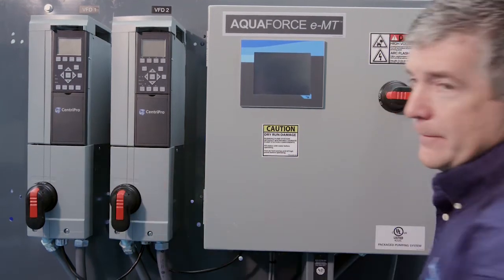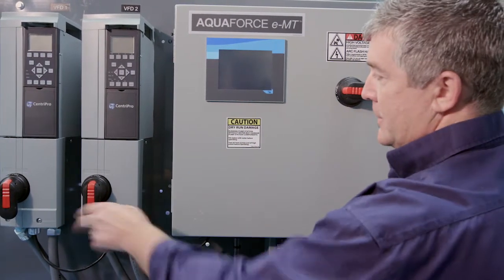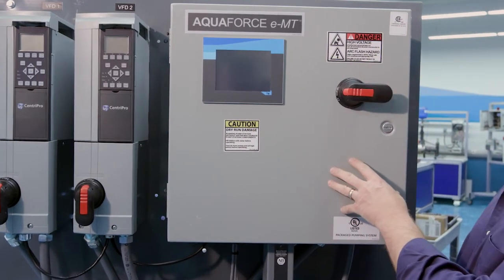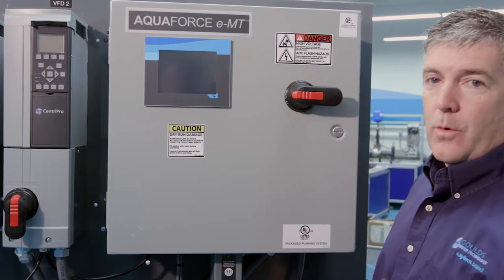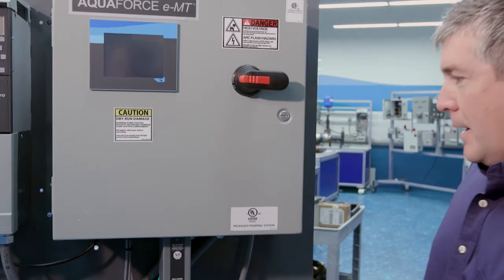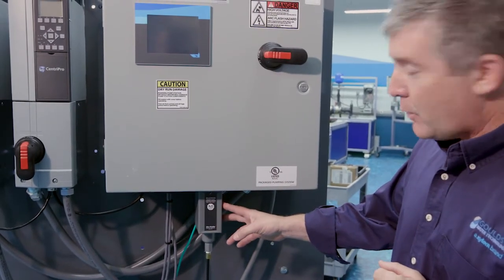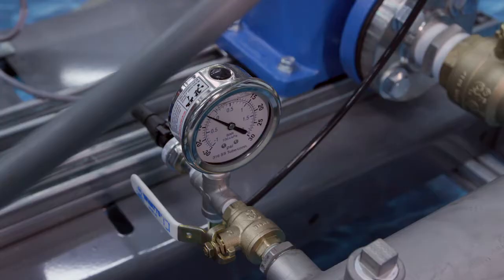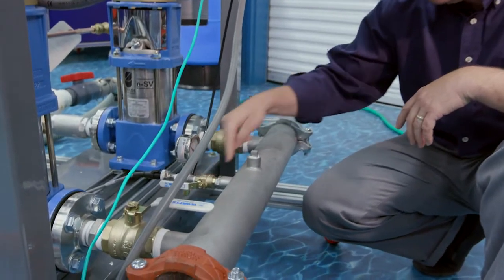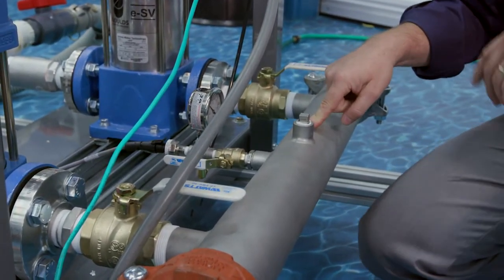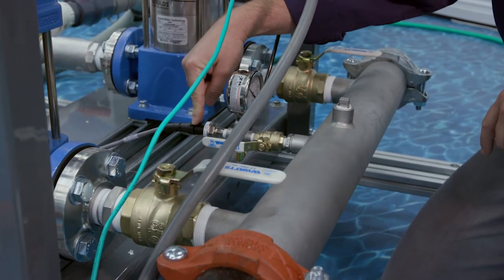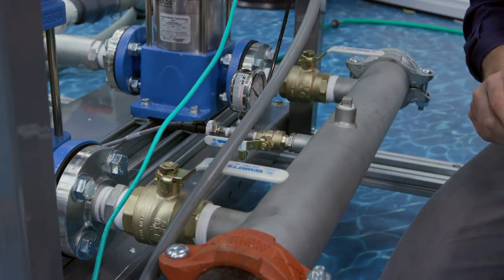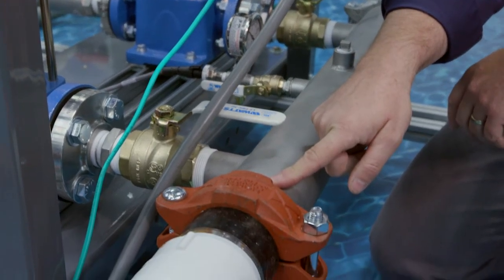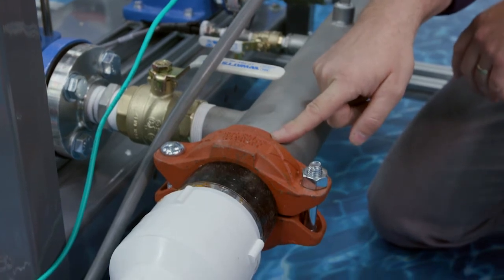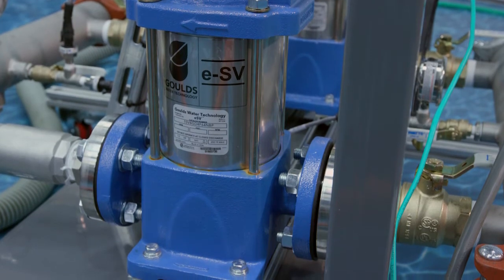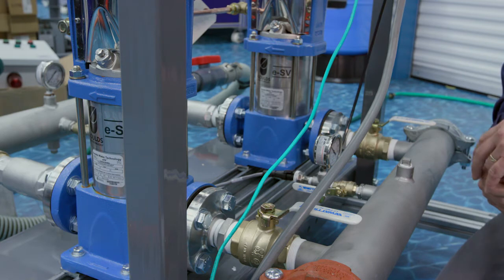First, let's talk about the two VFDs, variable frequency drives, with disconnects. Over here is your control panel, again with a disconnect, and a PLC, or programmable logic controller. As we move down, let's talk about the low suction pressure switch. The low suction pressure switch is connected here and comes off the suction manifold. Also, in this particular demo, we have a low suction pressure transducer. Some of the other components of the system are grooved fittings, so 304 stainless grooved type fittings. And on the pump side, for this particular unit, we have two ESVs, vertical multi-stage booster pumps.